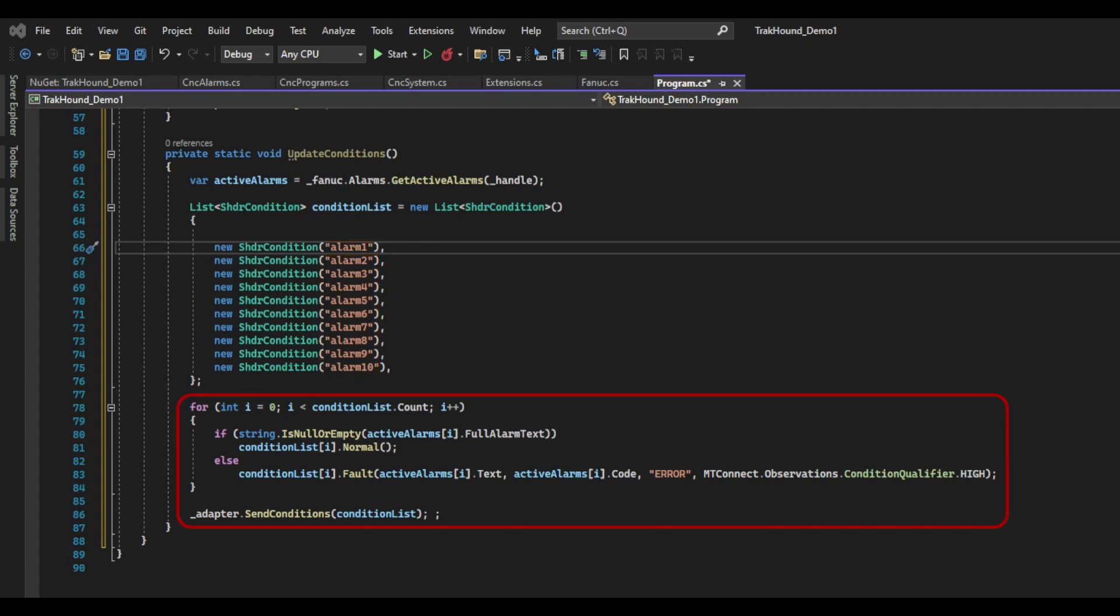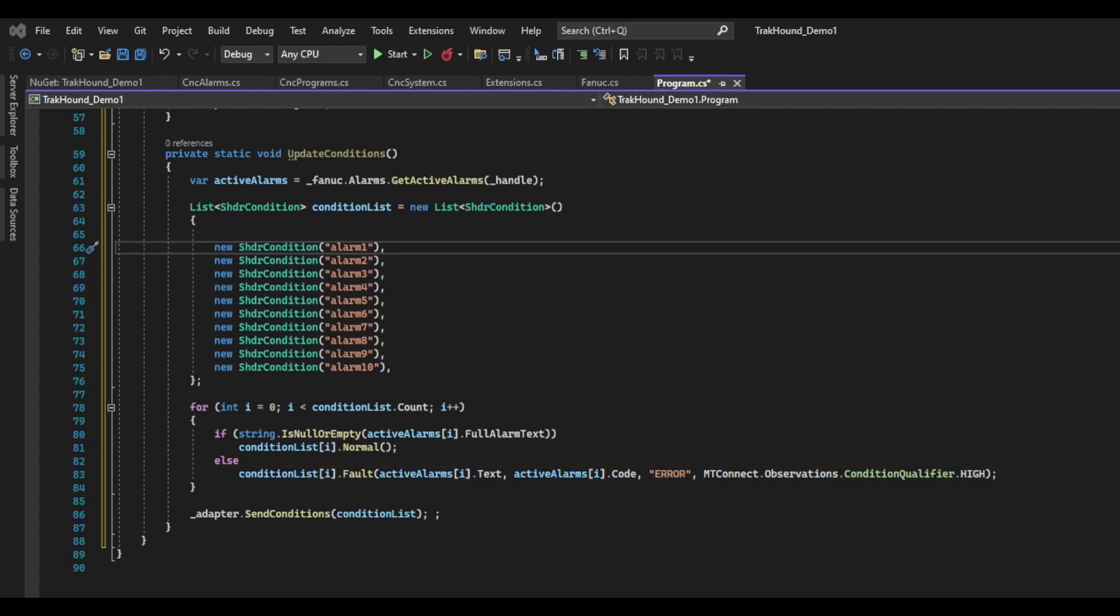Next, I am going to create a for loop and iterate over all the conditions in the condition list. If any one of the alarms is not in an active alarm state, the alarm text will simply contain an empty string. So inside the loop, I will check to see if the alarm from the active alarms list is empty or null. If it is, I will set that condition to normal by calling the SHDR conditions normal method, which indicates there is no warning or fault on the machine. Otherwise, if the string is not empty, I am going to call the fault method. The fault method takes four arguments. The first argument is going to be the fault text. Next is the fault code. We then have the severity of the fault. I put error, but you could specify something else such as critical or information. The last argument is going to be the condition qualifier. Basically, this says whether the fault is high, low or not specified.